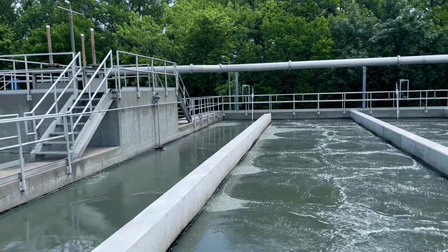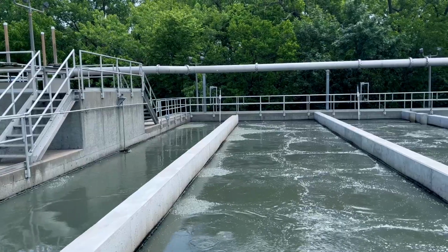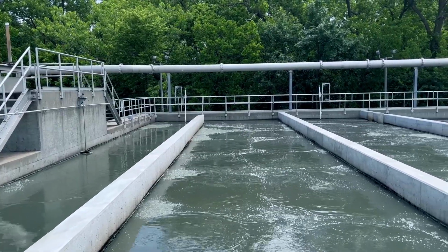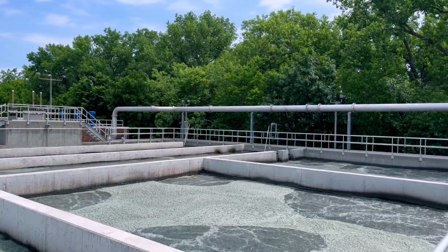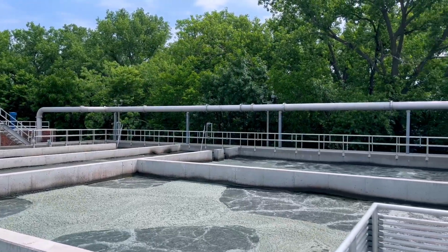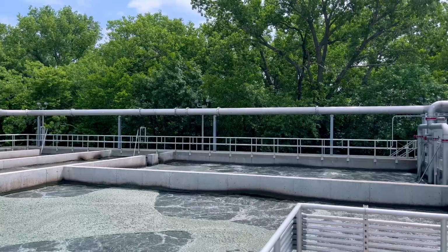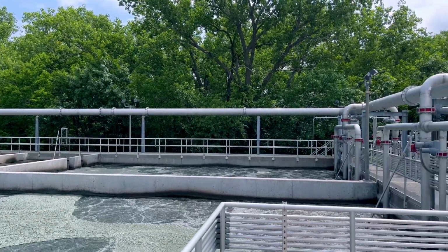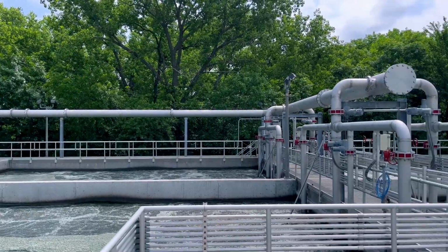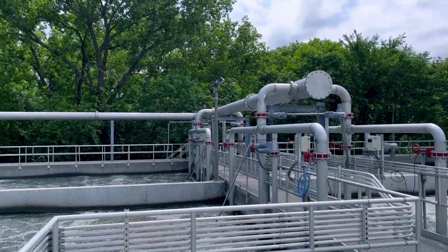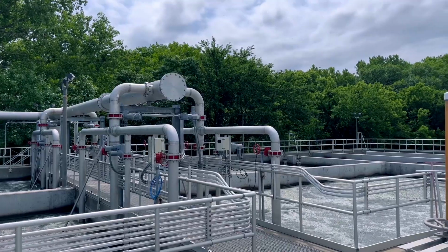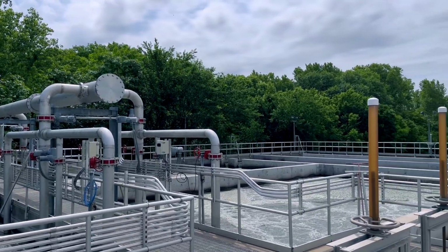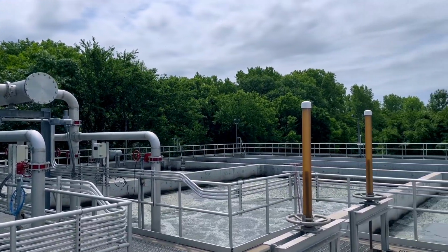The wastewater moves through the next 2 channels where bugs are removing nutrients through an anoxic stage where water goes through the nitrogen cycle. The wastewater then moves from the anoxic zone in the 2 channels to the aeration basins. Oxygen is introduced into the water, creating an aerobic zone. The aeration basins allow for growth of bacteria, creating a higher treatment capacity than traditional treatment processes. In these basins, biochemical oxygen demand is removed and ammonia is converted to nitrates.